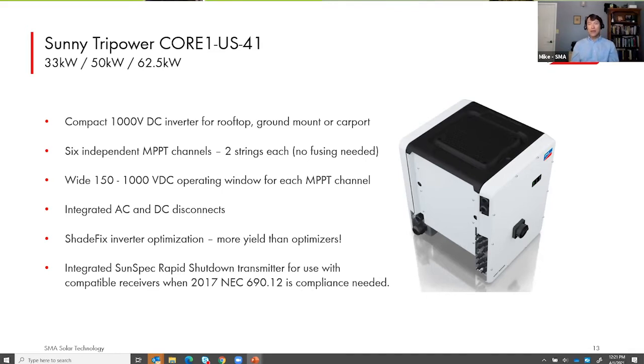That is an update to the maximum power point tracking algorithm to ensure that each and every input on the Core 1 is being worked at the highest possible power point, even in conditions of partial shade. And that is all driven as a sweep function in the inverter. It doesn't require any module level power electronics to achieve. So it provides the flexibility.